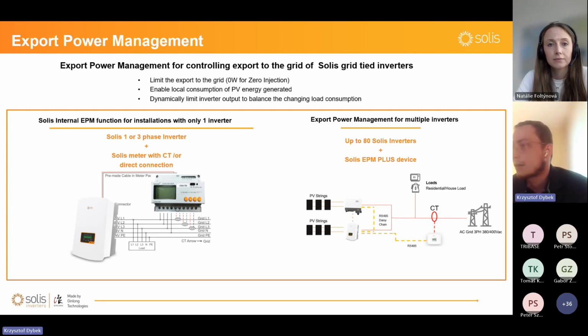So my advice is do not extend CT cables, because most likely this causes losing communication and reading will be wrong. It's better to just extend RS485 communication and put the meter where it should be, near MCB. So yeah, this clearly shows the basics of this.